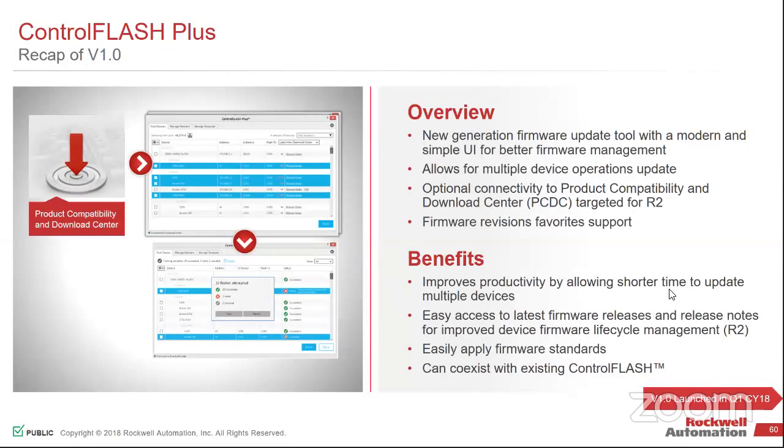So what Control Flash does is you plug in and it brings up an RSLinx, essentially a client browser, and it'll go down and it'll find whatever you're plugged into. And then it'll say, what version of firmware is this thing? What version of firmware do you have on your computer? And then there's a go button, and then there's a flash to drop down menu. You can say flash to latest and just click that for everything and auto update everything to latest, or you can just pick a version of whatever you have on your computer.